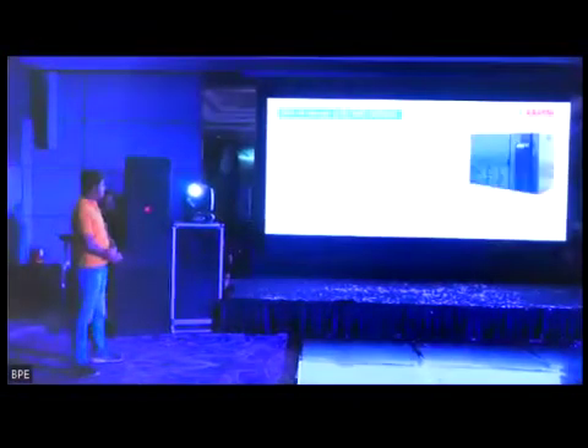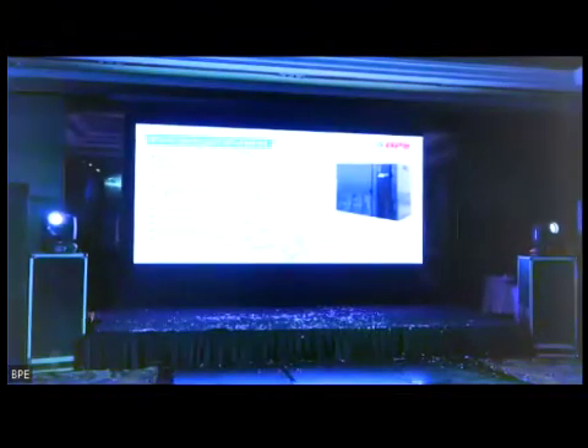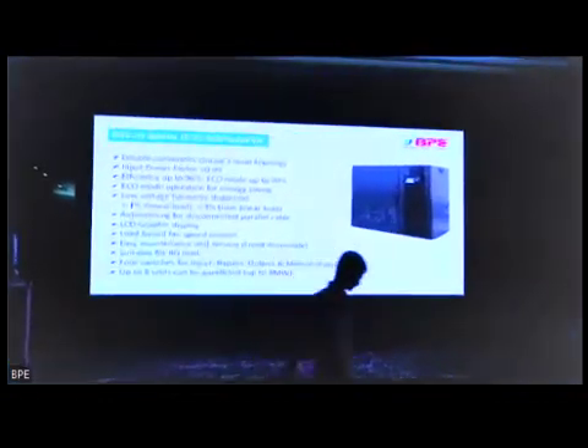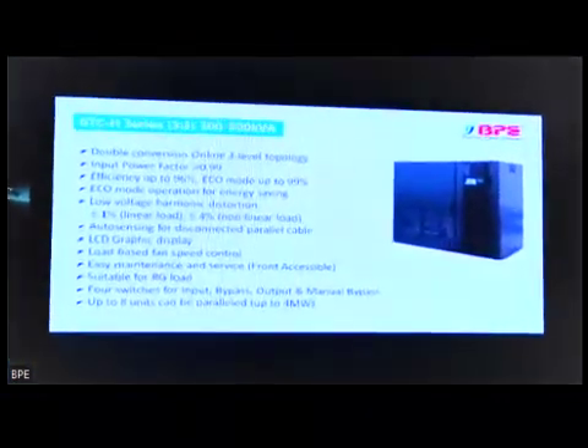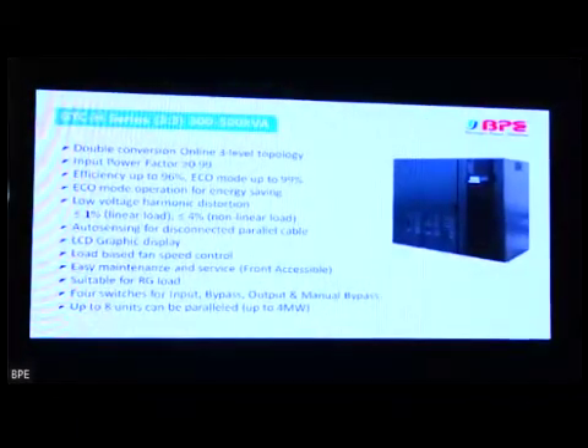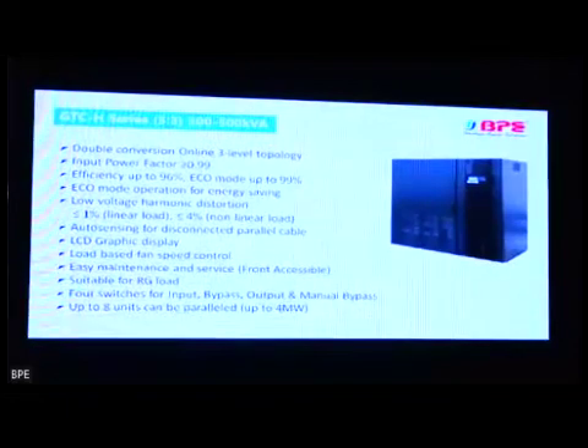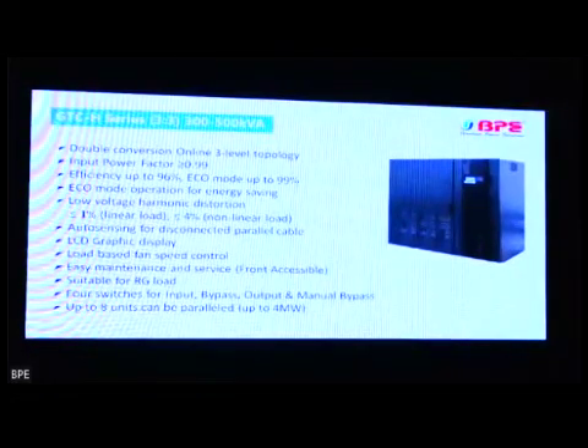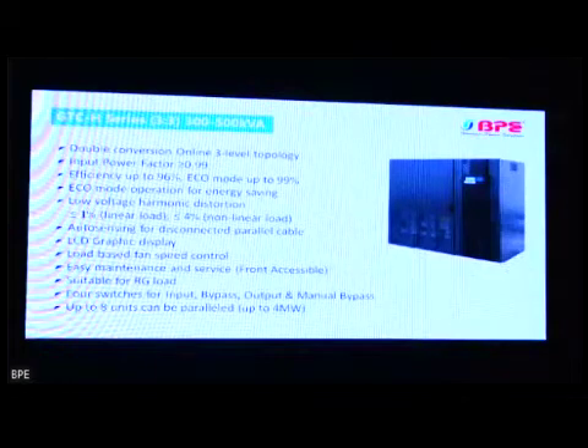So we are talking about the GTX series, which is from 160 kVA to 300 kVA, and we have seen this video. Now we have three-phase UPSs, megawatt solutions. This is basically for the bigger requirements. We have the GTC-H series starting from 300 kVA up to 500 kVA. This is double conversion online 3-level topology, with an efficiency of 96%, which is the online double conversion efficiency. Eco mode efficiency is 99%.